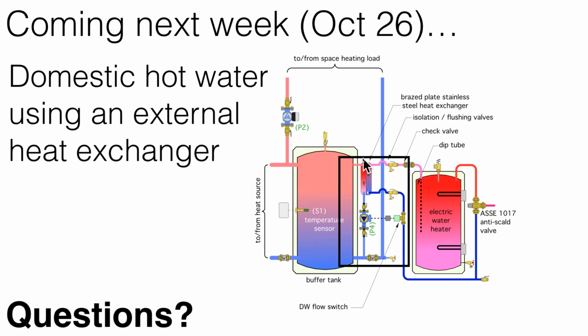The thing I would stress with the heat pump, again, is low water temperatures, simply to run the heat pump at less stressful levels. If we're trying to get 130-degree water and it's 10 below zero outside, it may be possible for the air to water heat pump to do that, but you're running it at some pretty high compression ratios. And like any mechanical device, the harder you run it, the shorter its service life is going to be. So, from a maintenance standpoint, we really haven't had any issues with this. The big takeaway is that at 130 degrees, you're at the upper envelope of what that compressor will tolerate from a refrigerant pressure standpoint.